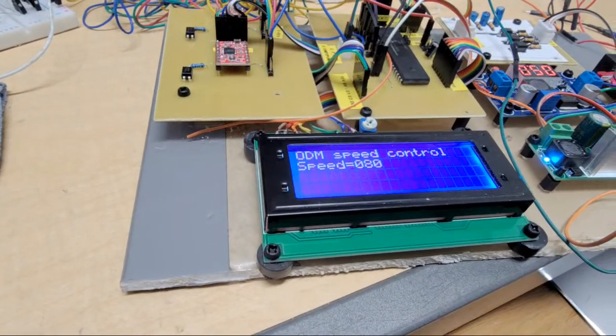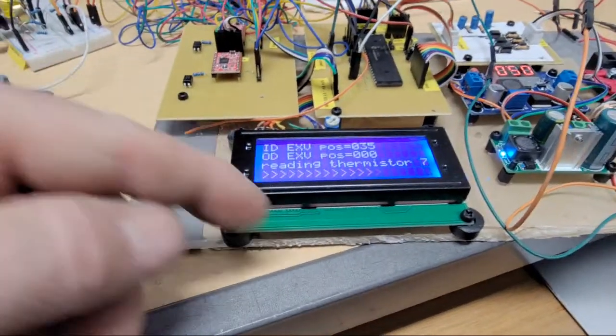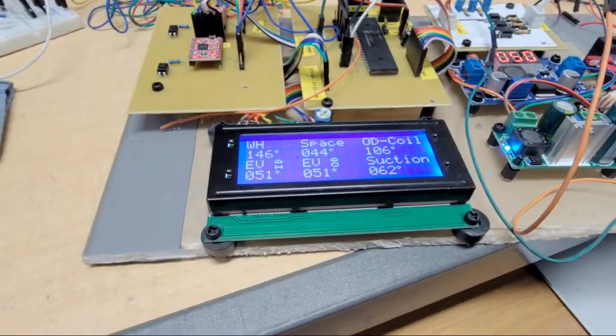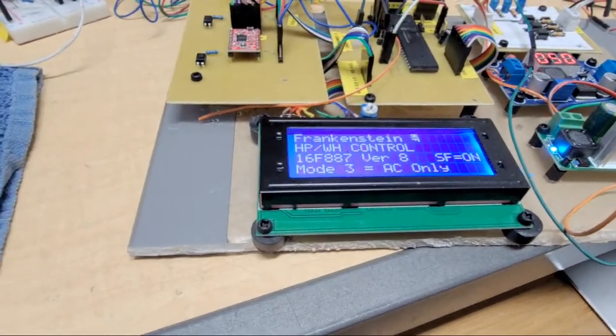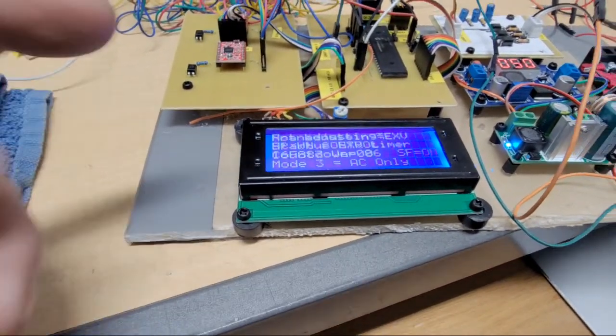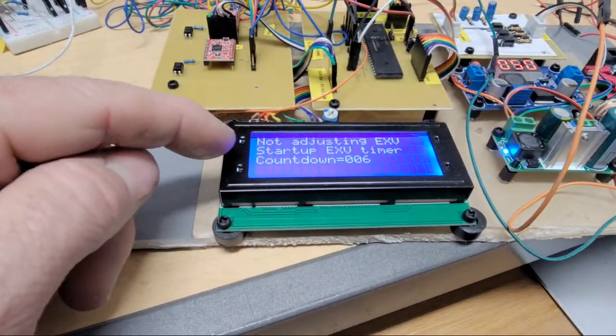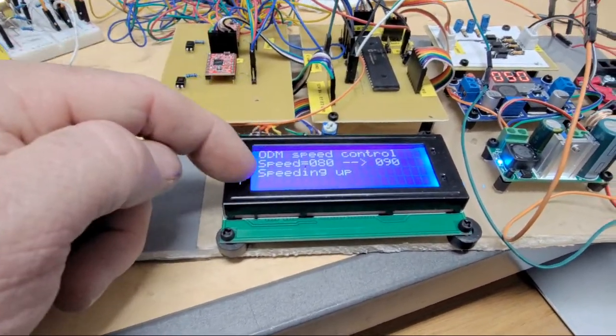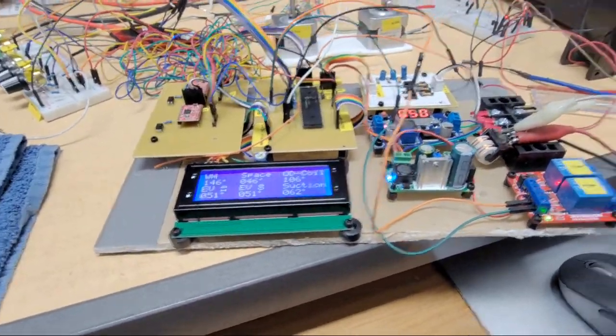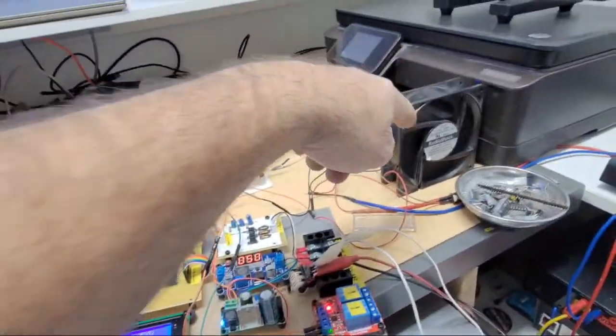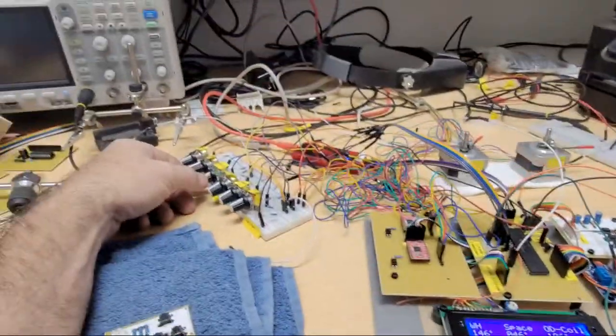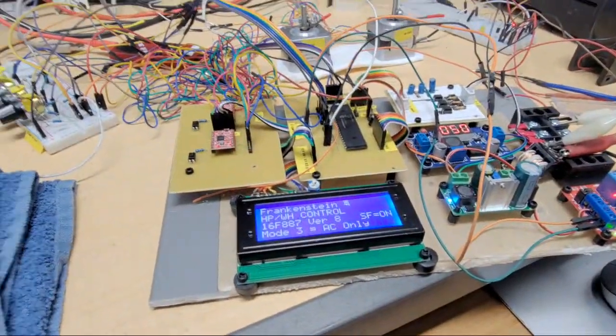So if I make the outdoor coil warmer, the next time it comes through, after it reads the thermistor, it's going to see that 106. That was basically the liquid line temperature I called out there, and it's going to start ramping up. There we go, speeding up the outdoor fan. TXV or EXV, it skipped a while. There goes the fan. I had the pulse width starting point a little low for this thing to start, just using a transistor to switch the negative side of it. Put that back into a neutral temperature there.